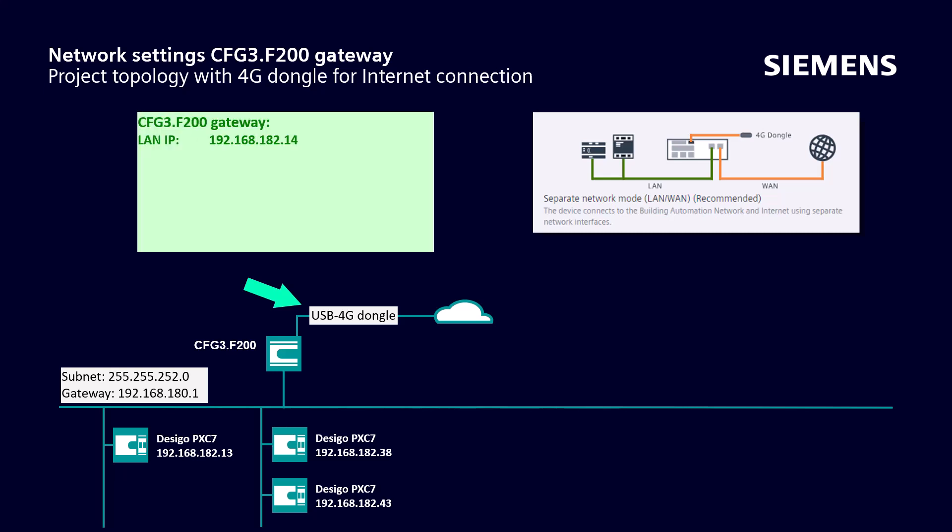The IP address for the LAN connection of the F200 device is defined here. This is the WAN IP address of the 4G dongle. The firewall settings refer to the default BACnet UDP port and the two already known TCP ports that must be opened to communicate with the Desigo Optic Web Client.